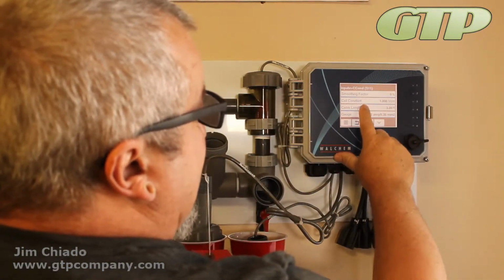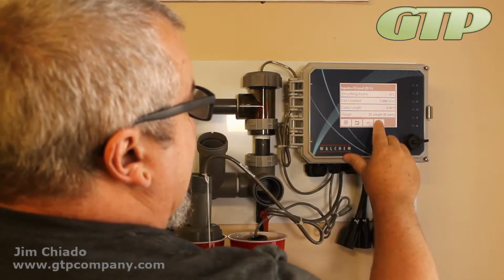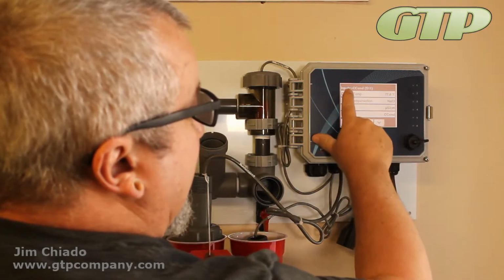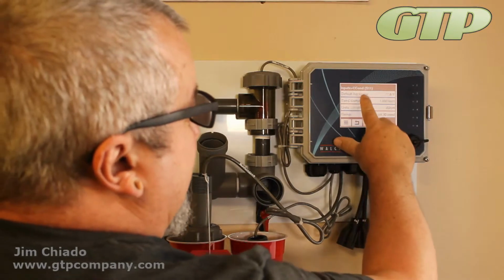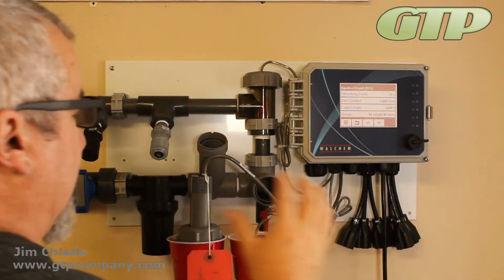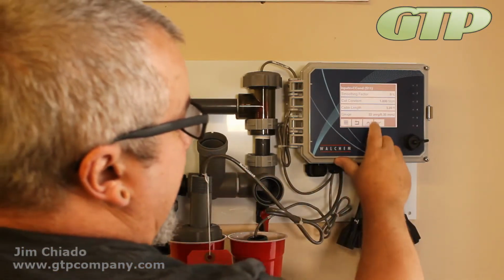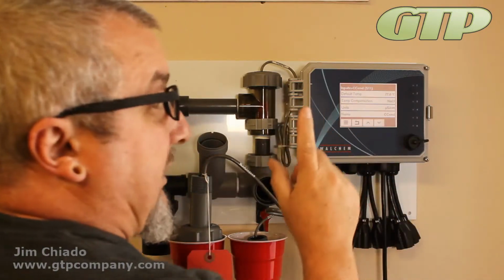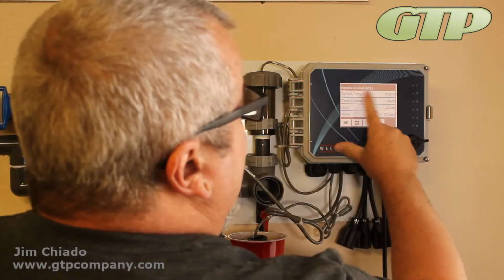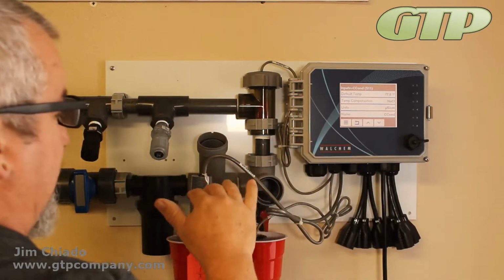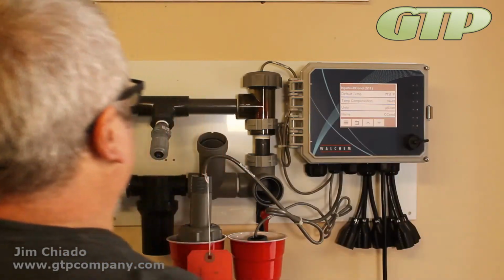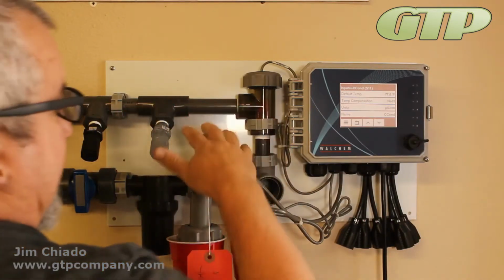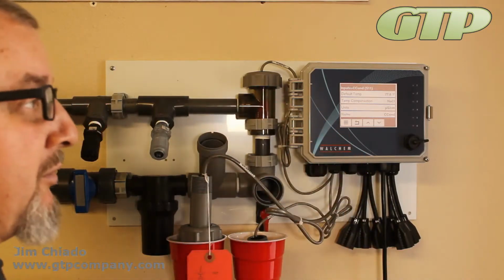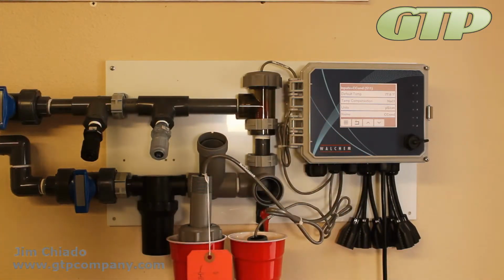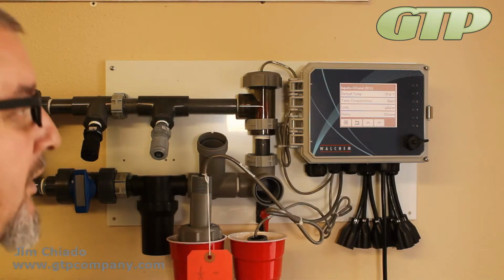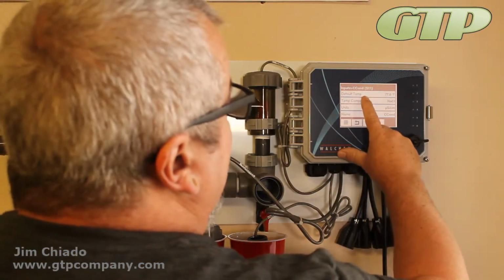The cell constant, the cable length, the cable gauge, and default temperature: these are based on the sensor that you've chosen. Make sure that they're right with what you have. Call the factory and we can help you out, make sure that they're right. Default temperature is if the temperature portion fails, go back to 77 degrees. This is a cooling application, but it could be a boiler, it could be pH, could be neutralization, could be an aquarium, whatever. You want to make sure and have that in there.